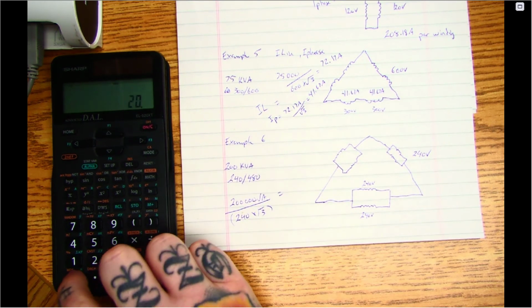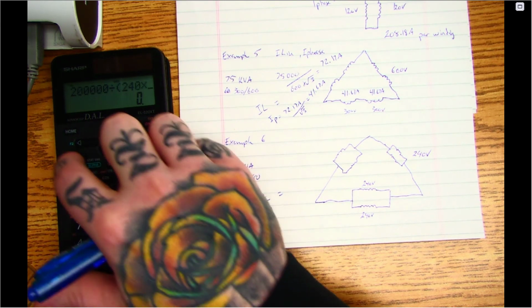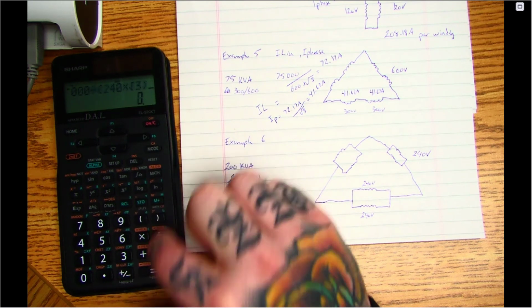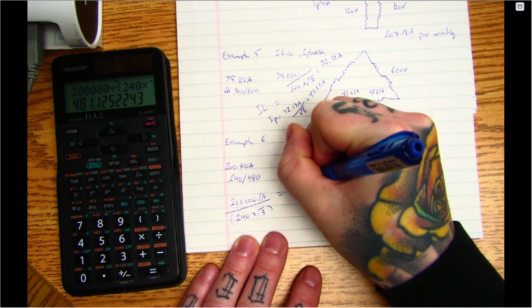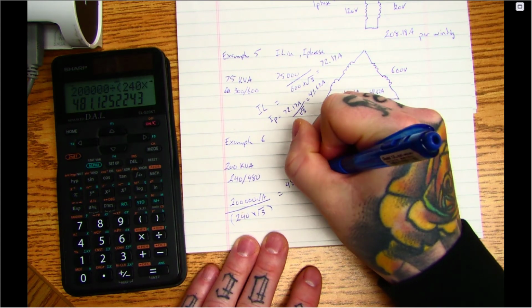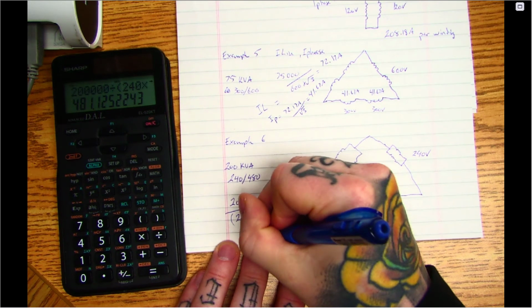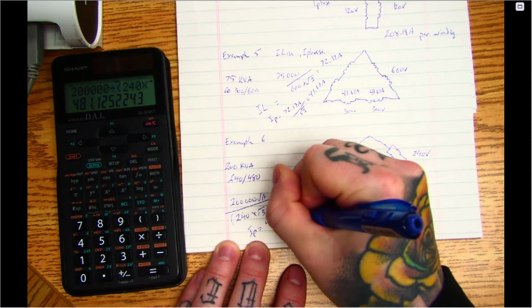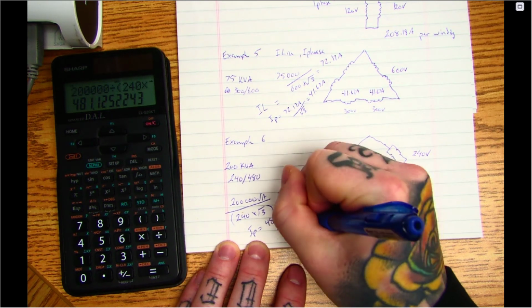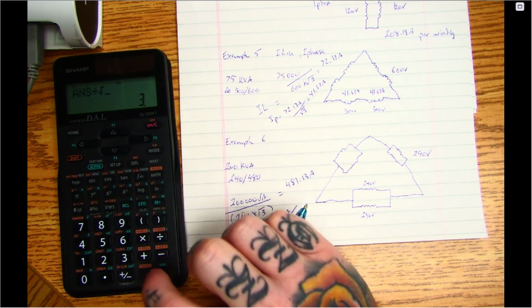So 200,000 divided by 240 times second function root 3, and I get 481.13 amps. And if I want I phase, I've got to use a root 3 relationship because we're in delta.